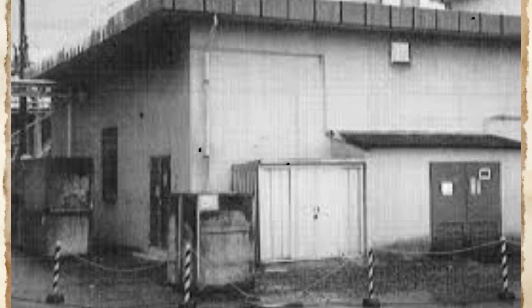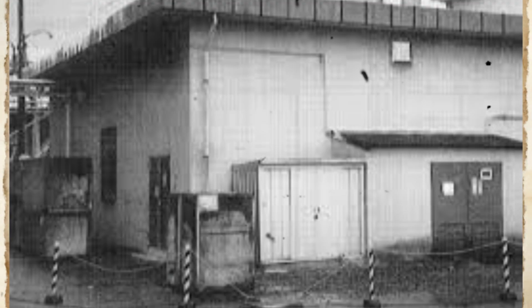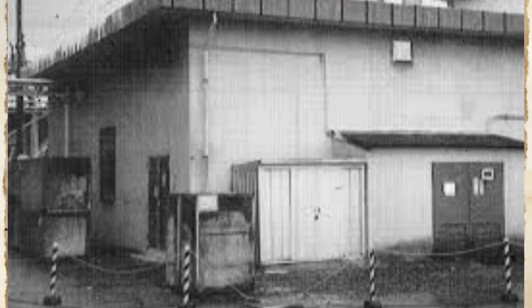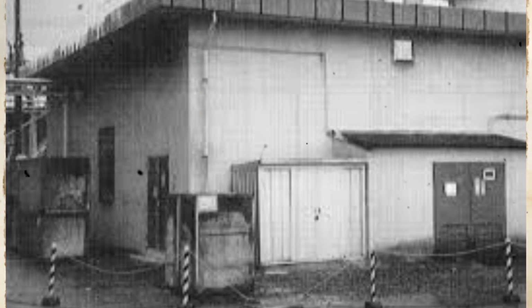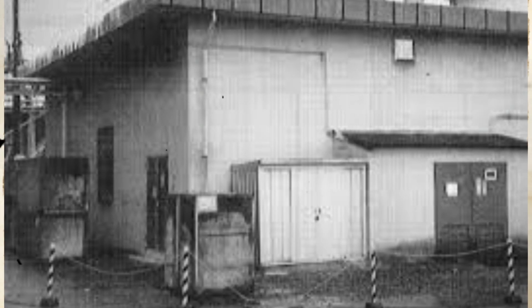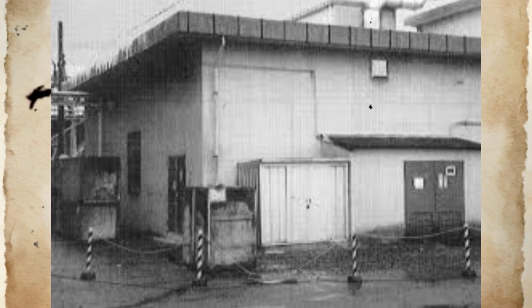At Fukushima Daiichi, seawater intake structures and circulating water pumps were damaged by tsunami flooding, eliminating the plant's ultimate heat sink capability. This meant that any heat added to plant systems, whether from decay heat, pump operation, or zirconium oxidation, could not be removed from the site. Suppression pools, designed as intermediate heat sinks for short-term emergency conditions, gradually heated towards saturation as they absorbed heat with no removal capability. Once suppression pool temperatures reached saturation, continued heat addition would cause boiling and steam formation, eventually leading to containment overpressure if not relieved.